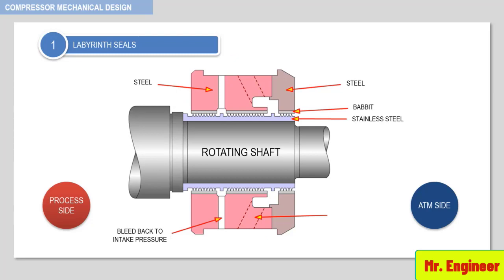Another port can be used to inject another gas at a slightly higher pressure than intake pressure. This prevents the process gas leakage, but results in the injected gas leaking both to atmosphere and intake, as depicted here.